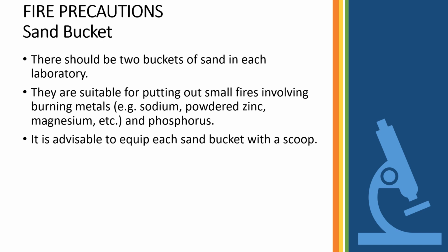Sand bucket. There should be two buckets of sand in each laboratory. They are suitable for putting out small fires involving burning metals. Examples: sodium, powdered zinc, magnesium, etc., and phosphorus. It is advisable to equip each sand bucket with a scoop.